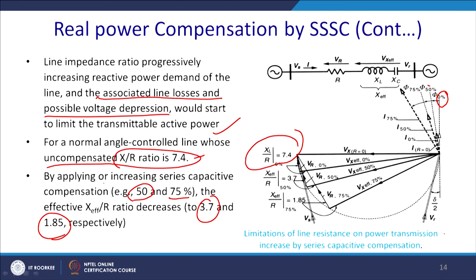And now let us understand the phasor as well as the circuit. By increasing the series capacitive compensation, let us say 50% or 75%, the effective X by R ratio gets decreased to this percentage as well as this percentage. Then what will happen? See, this is phi equal to 0, this is the compensation, this is 75%, this is 50%, and you can see this is R equal to 0 and this ratio is actually 7.4, this X by R ratio is 3.7, this is 1.85, and in this way it changes. Then what happened? This poses the line resistance, and the power transmitted is increased by the series capacitive compensation, and our assumption no longer holds good that the line is predominantly inductive.